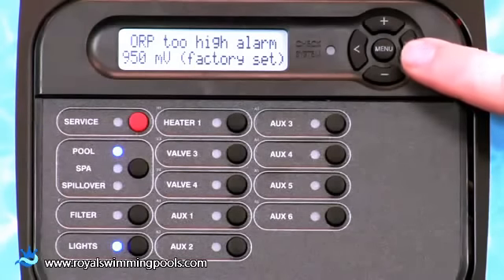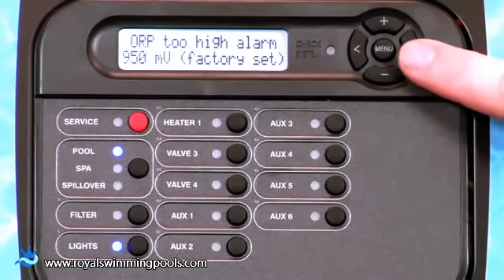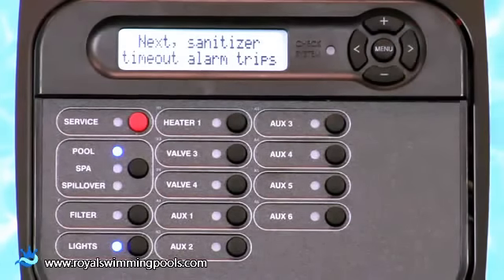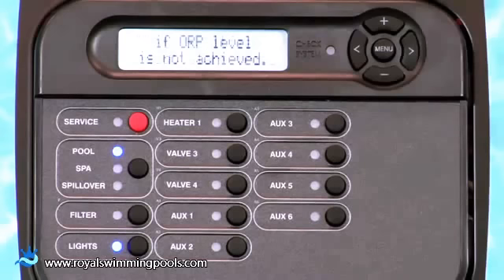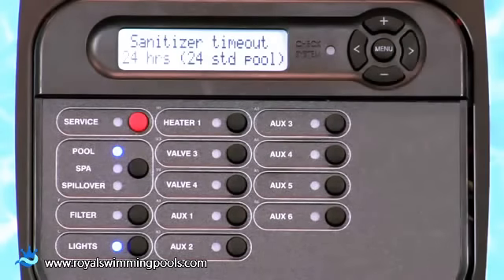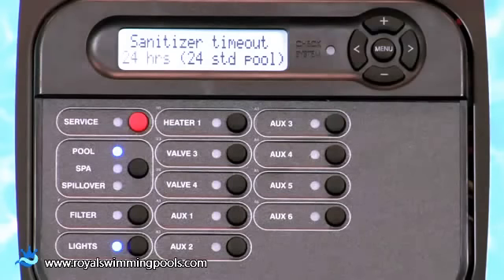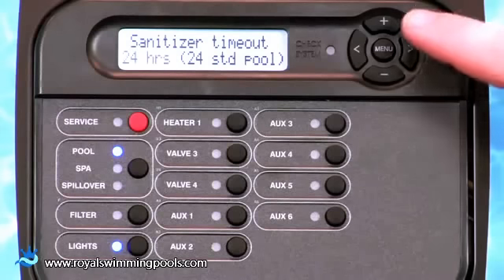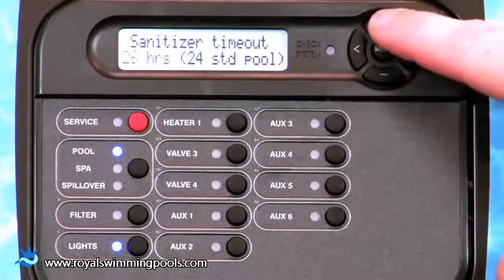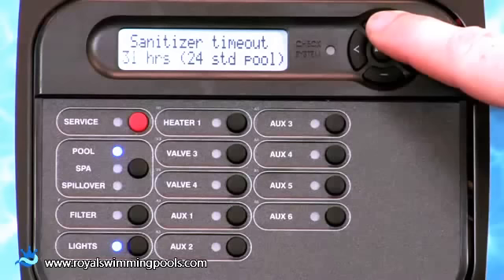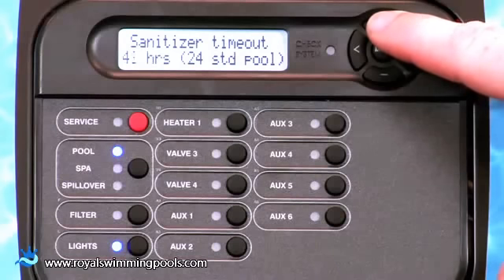Pressing the right arrow key three times moves through the next two screens where the Chemistry Wizard explains the function of Sanitizer and ORP timeout. The Sanitizer Timeout 24 hours screen allows you to set the maximum amount of time that the ORP control will attempt to increase the sanitizer level before an alarm. Pressing the plus or minus key will change the timeout from anywhere between 1 hour and 96 hours.